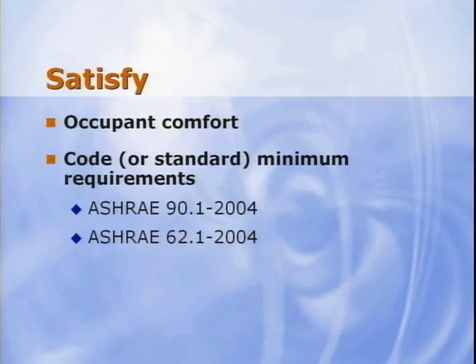So, what are the standard requirements for this type of system? First, we'll assume that the space comfort is to be maintained and that the base system satisfied the code or standard requirements. Next, local codes differ all over the country, so instead we'll use ASHRAE standards 90.1 and 62.1 as the basis for setting our typical system today. This choice has an additional benefit. If the project is considering LEED certification from the U.S. Green Building Council, both are prerequisites. So using them to define minimum requirements is a good start. We won't go into all the requirements or exceptions here, simply hit the highlights. Justin, please take us through these 2 ASHRAE standards.